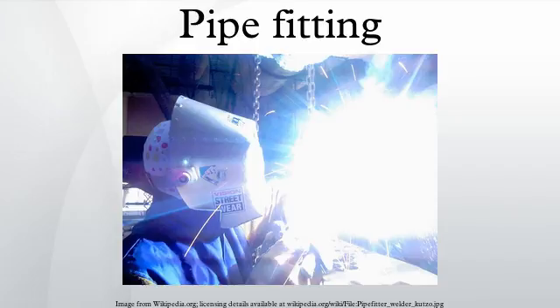Rigid copper is a popular choice for water lines. It is joined using a sweat, compression or crimp-pressed connection. Rigid copper, rigid due to the work hardening of the drawing process, cannot be bent and must use elbow fittings to go around corners or around obstacles.